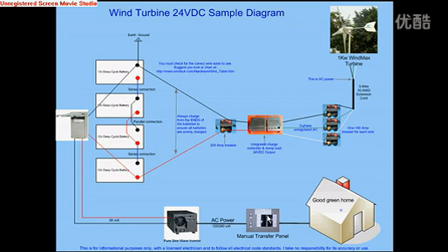The manual transfer switch would avoid the possibility of you trying to feed one circuit from two different power sources, i.e. the commercial power from the electric company versus your own power. There are other ways to do this, and I will do diagrams showing a grid tie inverter where this is unnecessary. But this is just assuming that you have a shed or a cabin or something of that sort. You just want to dedicate the light circuits in your home for this. There is no reason to go grid tie if you don't want to. You simply have a manual transfer panel that chooses power from either your battery bank and your wind versus the power from the power company.